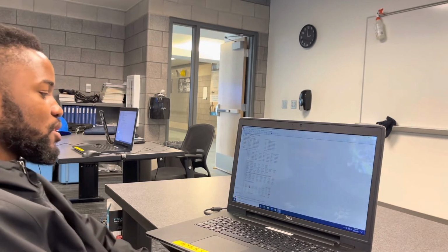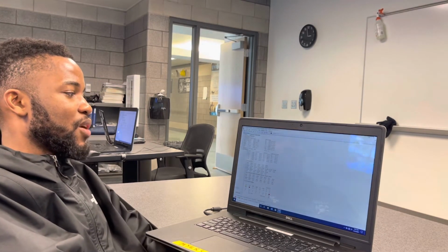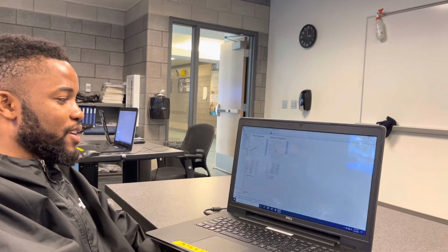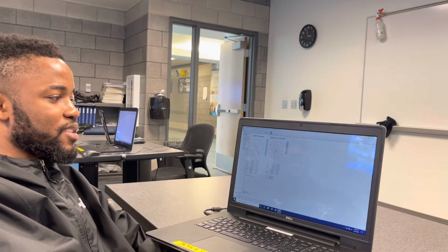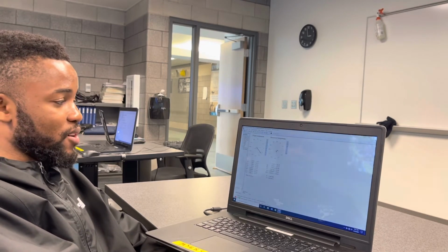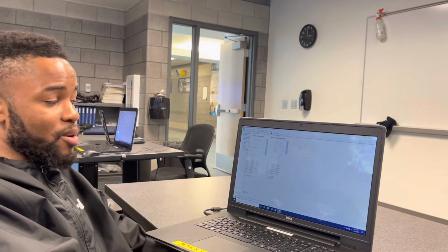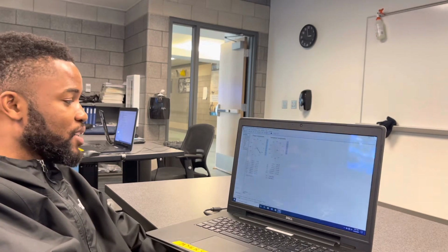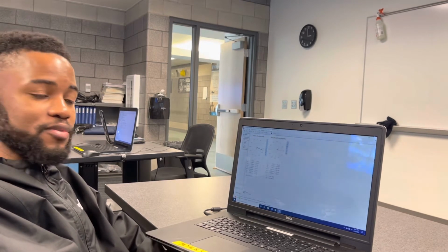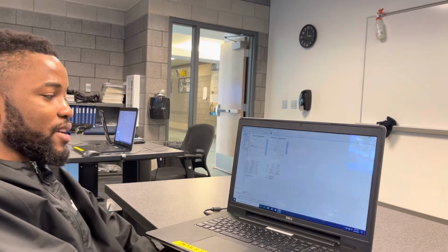input or output. So now you can also come to phasors, like you can see how they are phasing. So phase component of the current, and then you can see the phase and the sequence component, because we have the phase current and then we have the sequence current. So you can see how the phase current and the sequence current are different, and what angle or to what degree they are different. And you can also see the frequency, whether it's off or is actually right on.